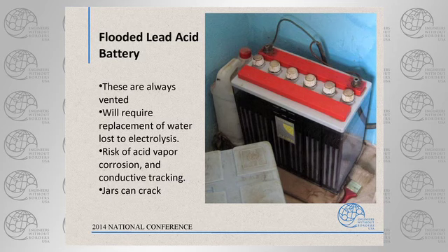All right, if we're going to talk about battery maintenance, we have to recognize the different types of batteries you may encounter. Most common, most economical, most widely available is our wonderful flooded product. We've got one here with a clear case where you can actually see the plates. These are always vented batteries. Venting means that as we put power into the battery, some of the power is used to break the water in the electrolyte down. The electrolyte in these batteries is water and sulfuric acid, about 1.22 to 1.25 specific gravity, so it's really stout acid.